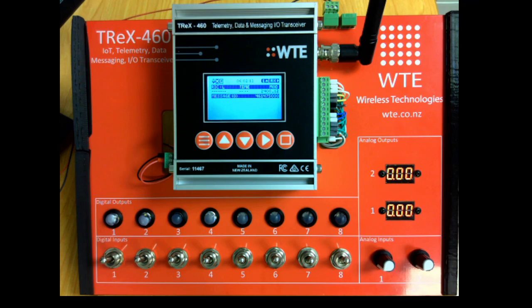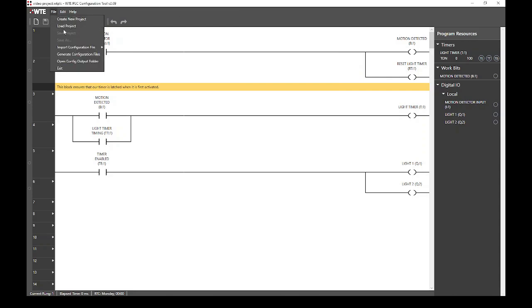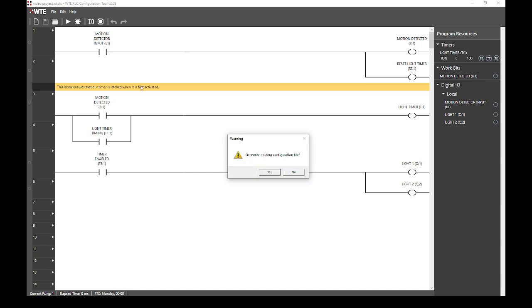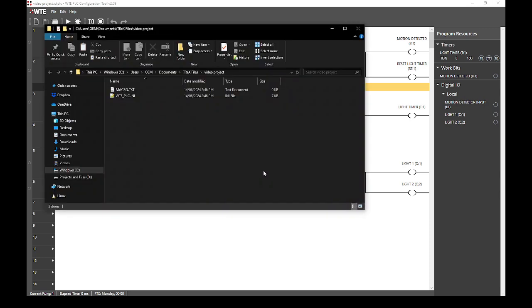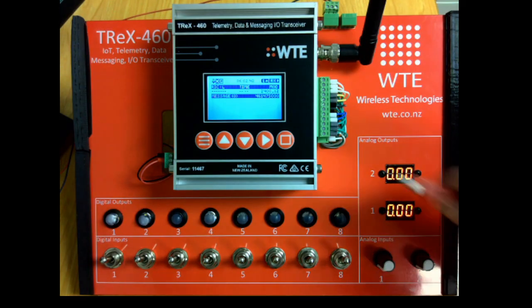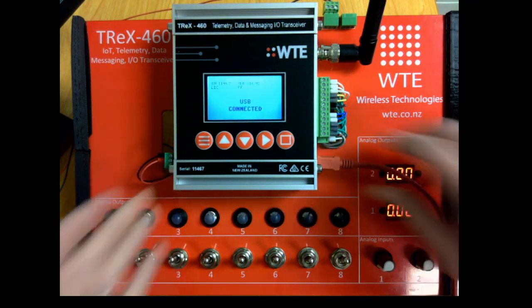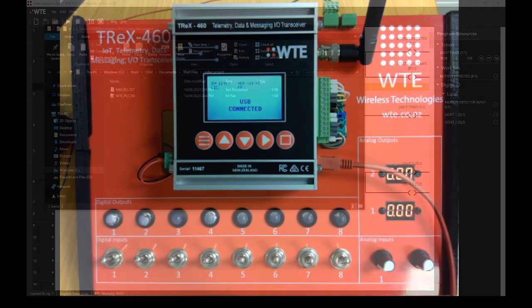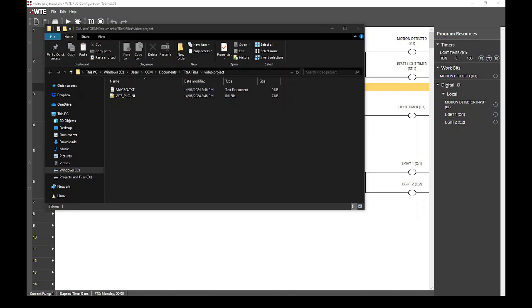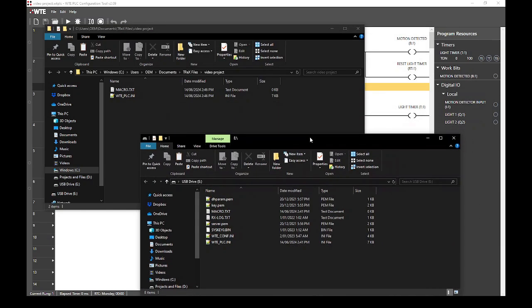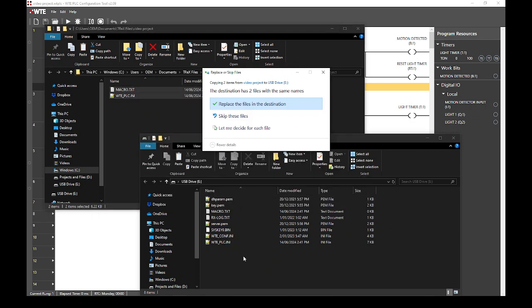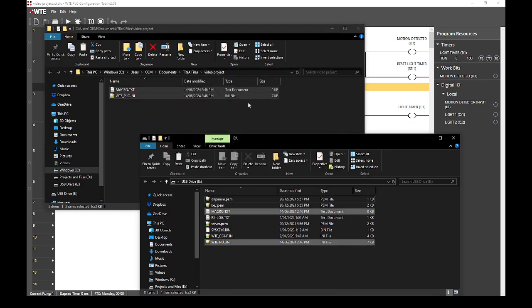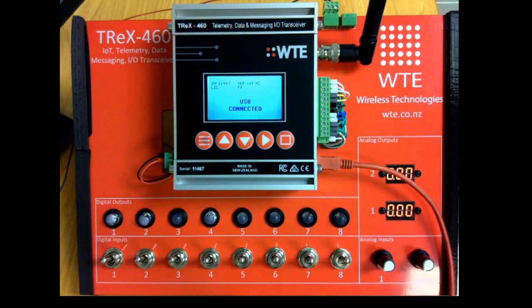Returning to the PLC configuration tool, we can now export our PLC program by selecting file, generate configuration files. If prompted to overwrite existing files, we select yes. We are now prompted to open the folder containing the exported files. We now connect to our T-Rex unit via USB. This will be detected by our computer as a mass storage device. We then copy our generated configuration files to the T-Rex's internal storage. We can now disconnect our T-Rex device.